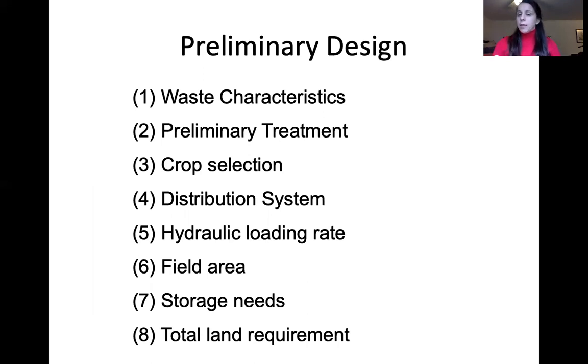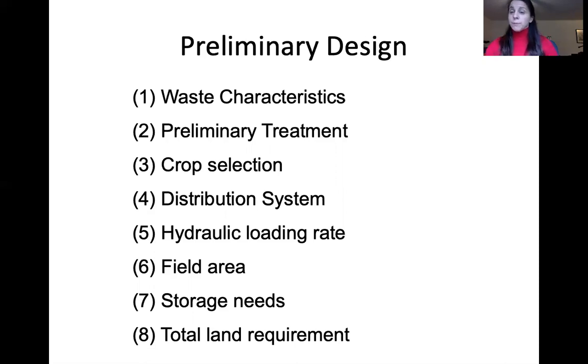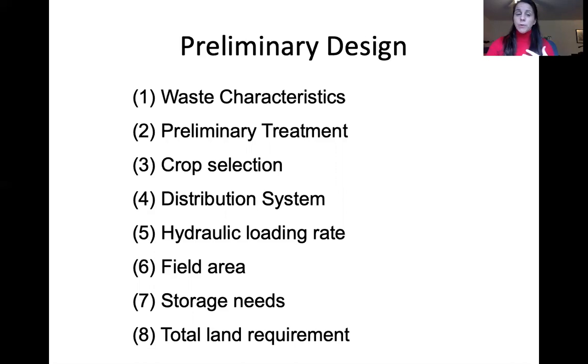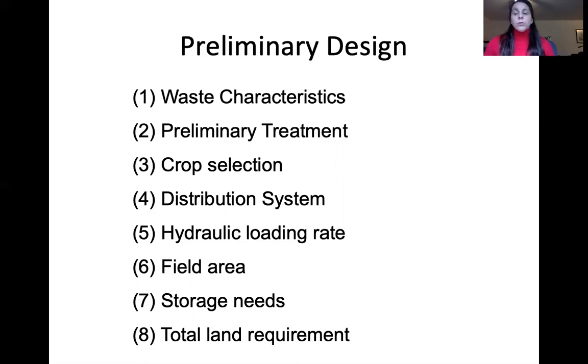For design of these systems, you need to know the waste characteristics, the level of preliminary treatment (secondary, primary, or pond/aerated), crop selection if applicable, distribution system type (surface or sprinkler), hydraulic loading rate, available area, and storage requirements. Storage needs depend on location — you won't have crops growing in North Dakota in winter. Total land required is based on the amount of wastewater your municipality produces.